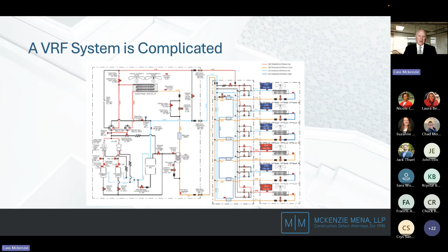Going back to the mechanical piping I talked about before, if your piping isn't installed correctly and you start getting failures, here's a building we represented where the piping was bending. Not enough refrigerant, lubrication, and coolant was getting back to the compressors, so they couldn't cool themselves, and you had units that couldn't get below 80 degrees, or even 76 degrees.